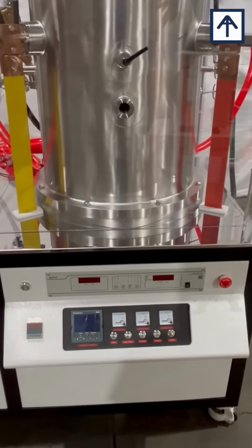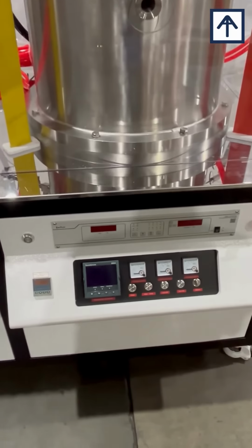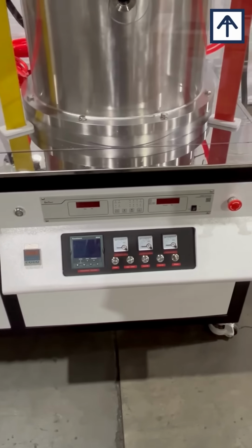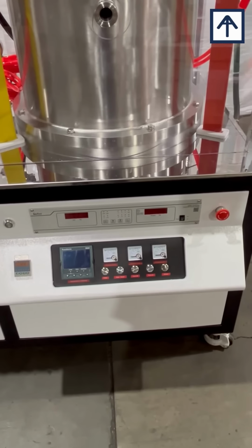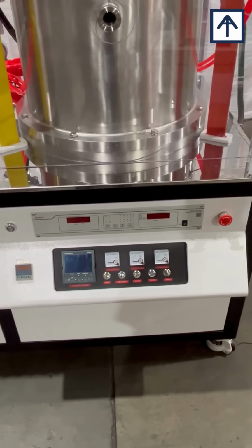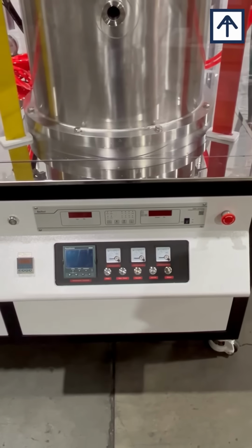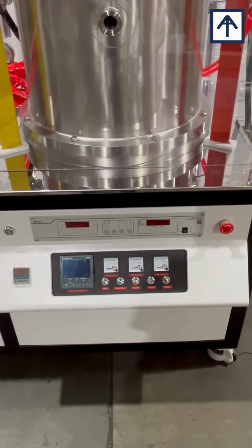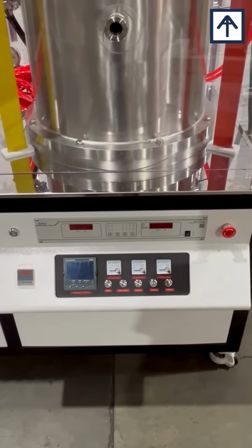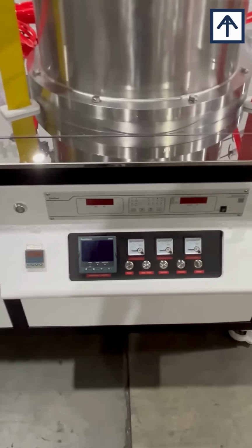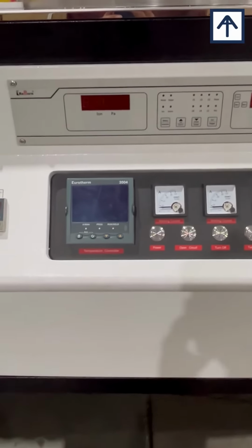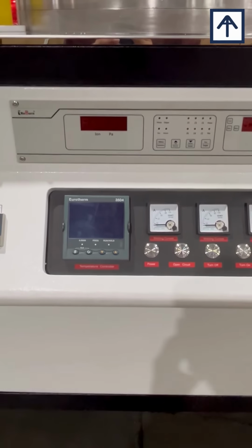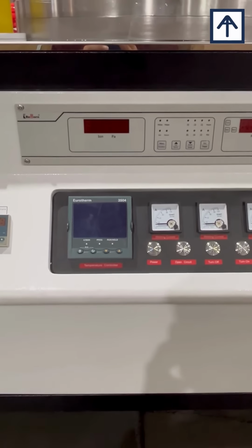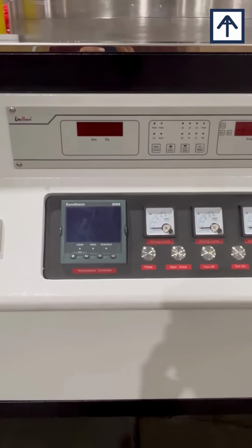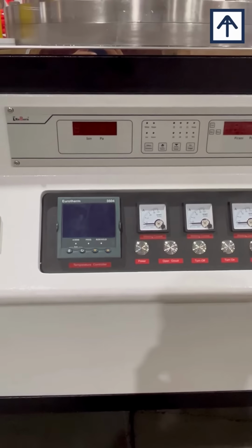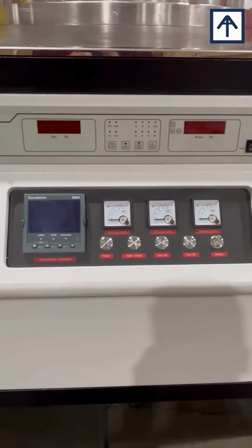Let's go over the key features and the safety features as well on the unit. So as you can see, the front control panel has an EMO switch, so that's an emergency stop, which can be used to turn off the unit if there is an emergency, or if you want to stop your process or any voltages going into the system itself. It comes with a Eurotherm 3504 controller, which is your primary heat control. It also has an alarm function where if it overshoots by a set point, it will just turn off the contactor, engaging the alarm system on the unit itself.